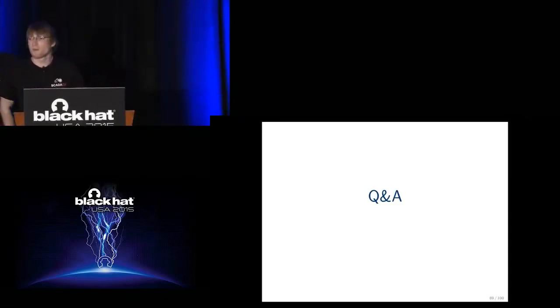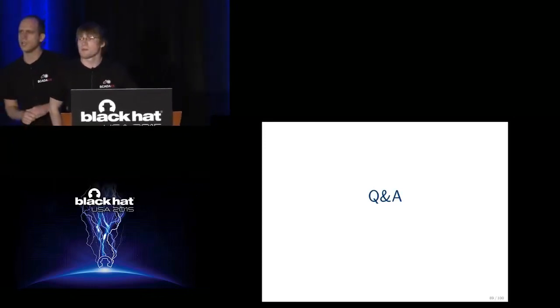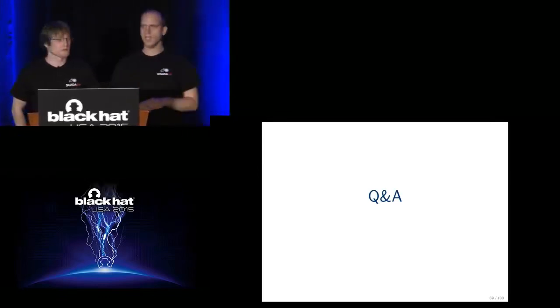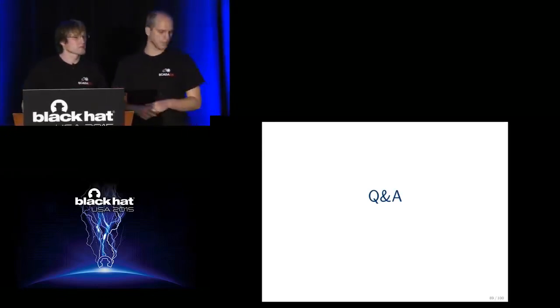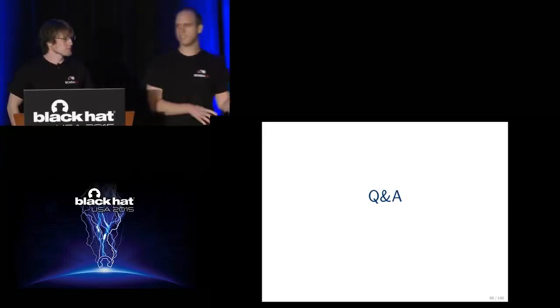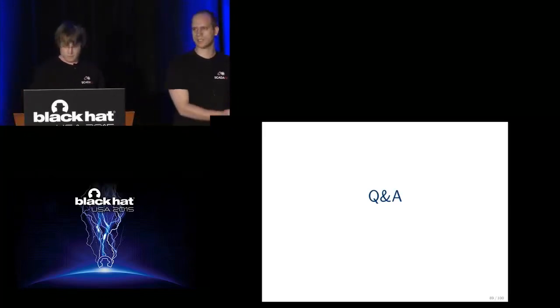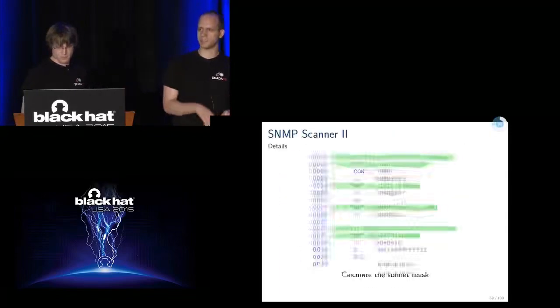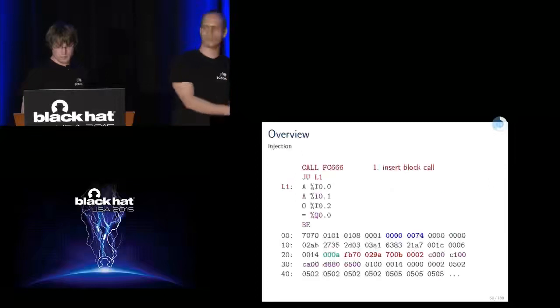When you push your new program, is there any interruption to the program that's already running on the PLC? Does that depend on how big your program was? Yes, that's a very good question. No, there's no interruption. We have shown it in the demo, right? The signal column lightning was controlled by the PLC, and we patched the OB1, and then the second one got active, but this was still working fine.